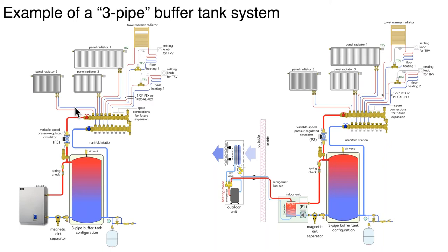This is the exact same distribution system just tied into an air-to-water heat pump. You do see I'm showing a check valve in both of these. The reason that check valve is there is when the heat source is off and the tank is warm, what we don't want to have happen is warm water migrating over here, cooling off and becoming denser. When water cools down, it becomes denser.